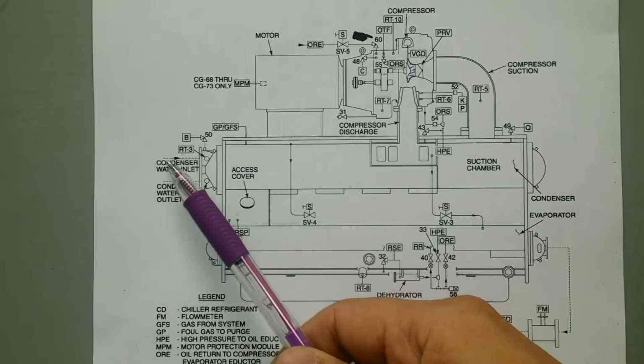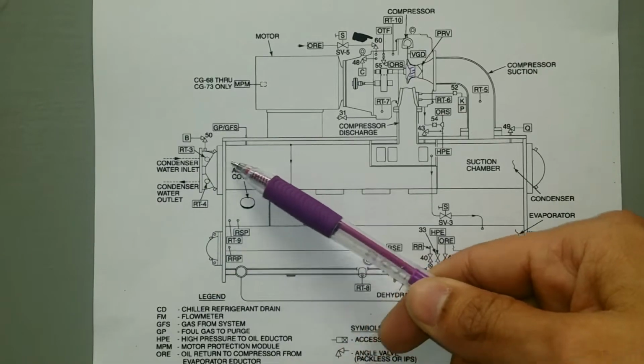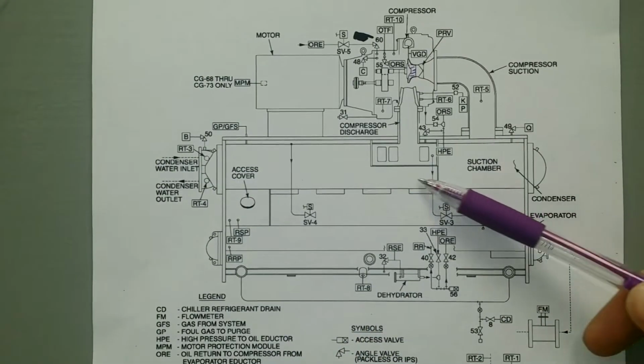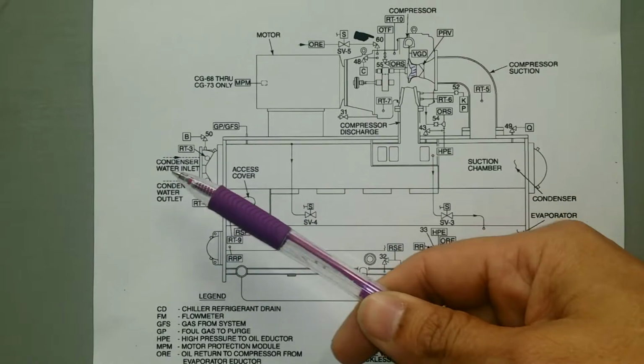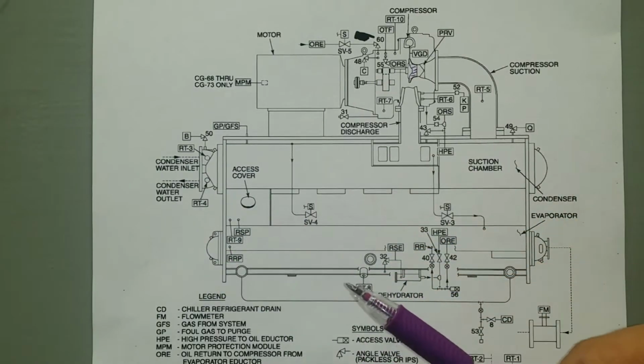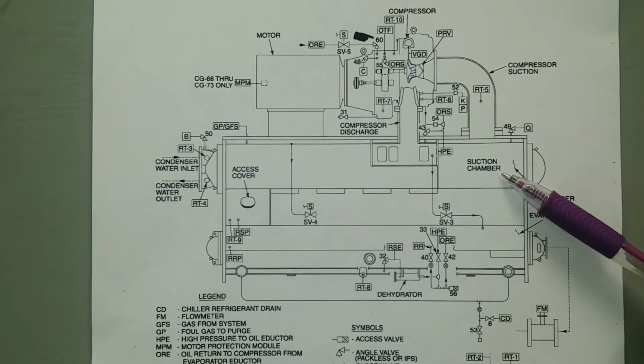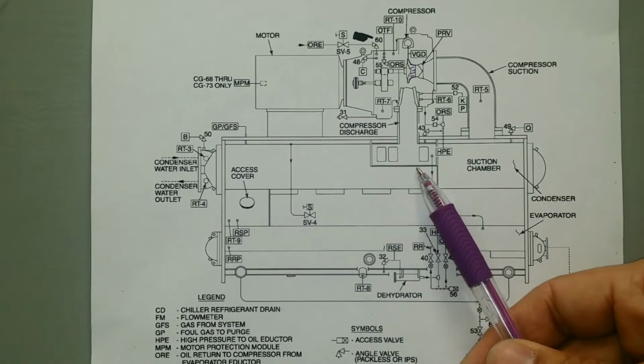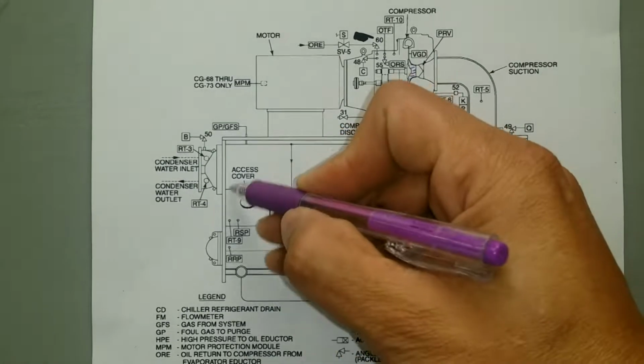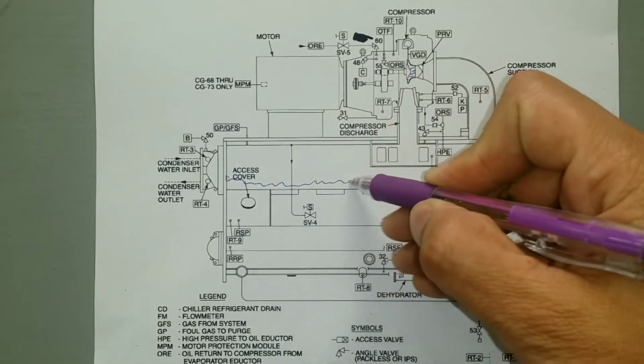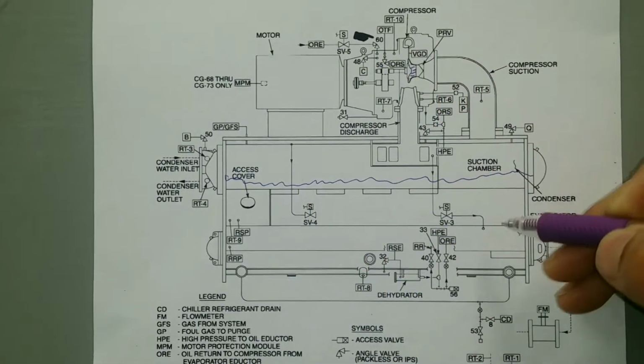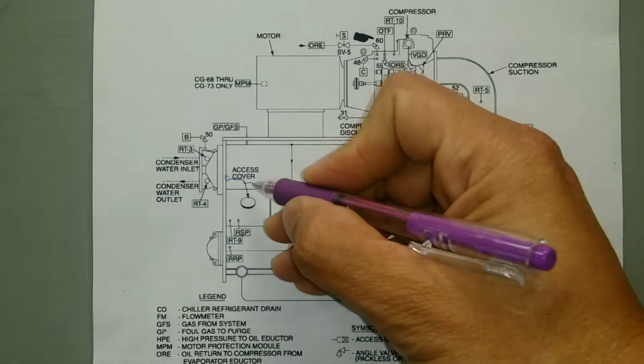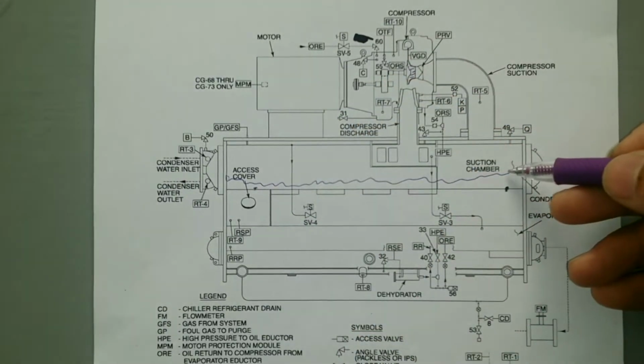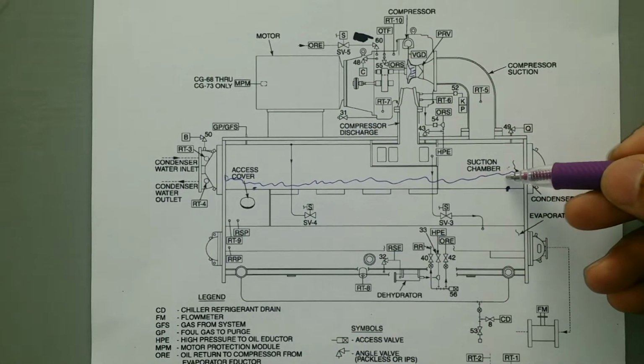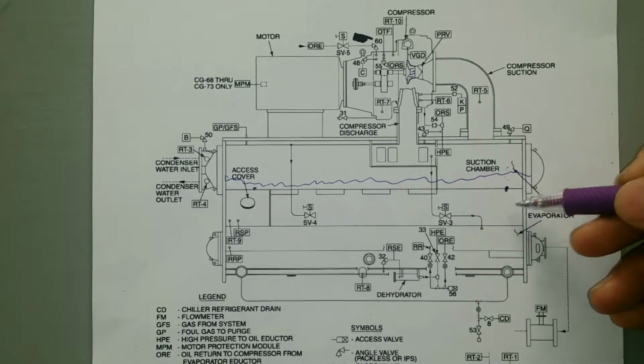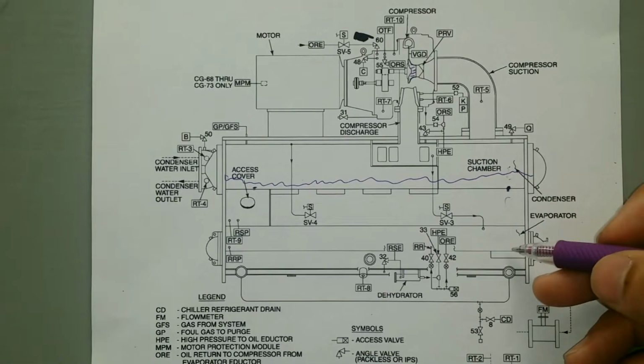So seawater comes over here through pipes or tubes. It comes in and it goes right back out through the same place that it came in. That's what the tech manual will say, that it's 2 passes, and it will remove heat from that high pressure gas. What it will cause is that the gas will liquefy and start filling the bottom of the condenser. Now, there are 2 orifices on opposite sides, and they will start allowing the liquid refrigerant to meter out into the evaporator.